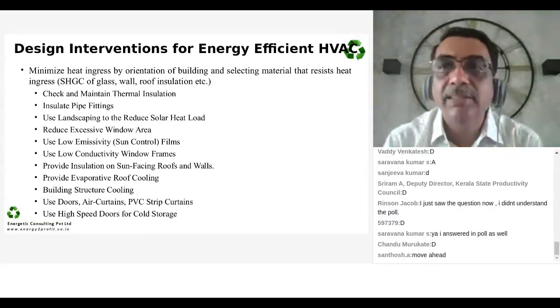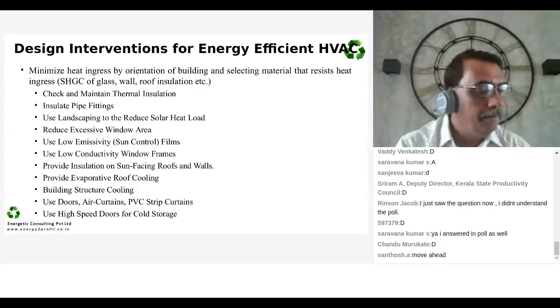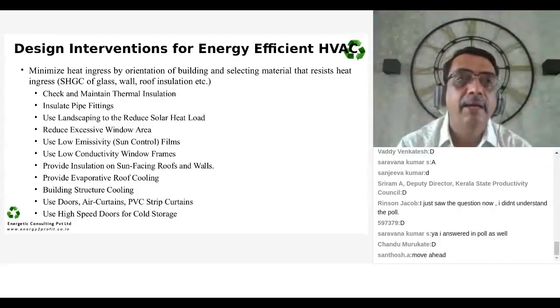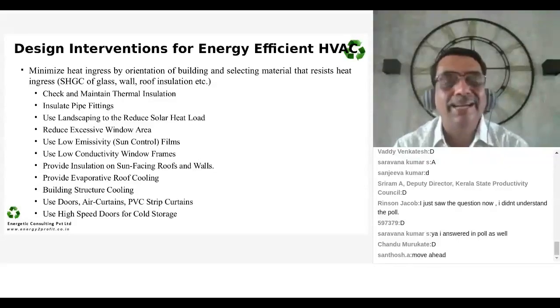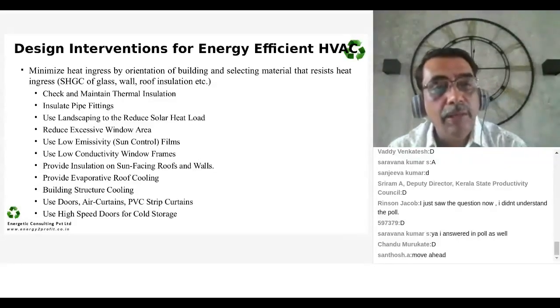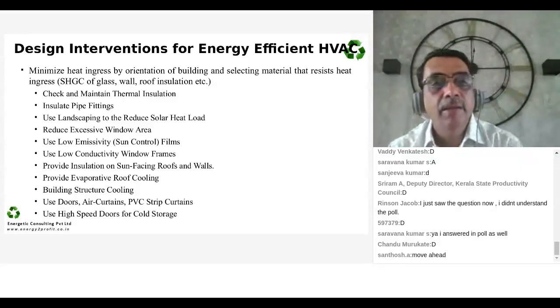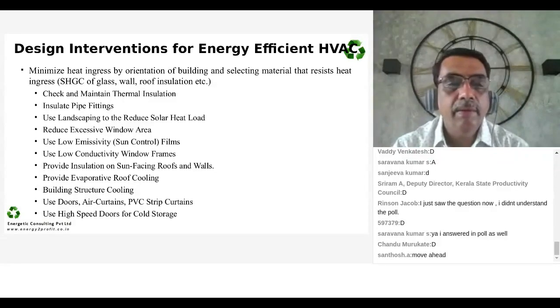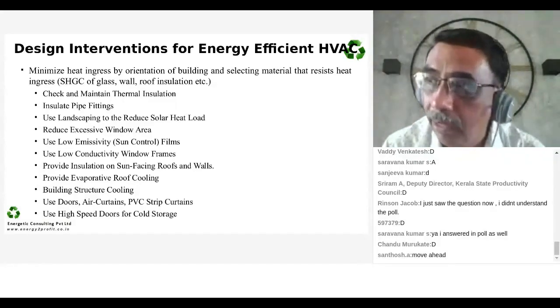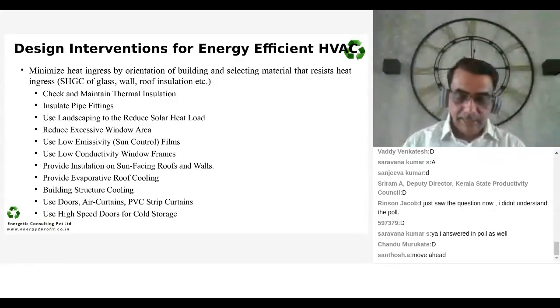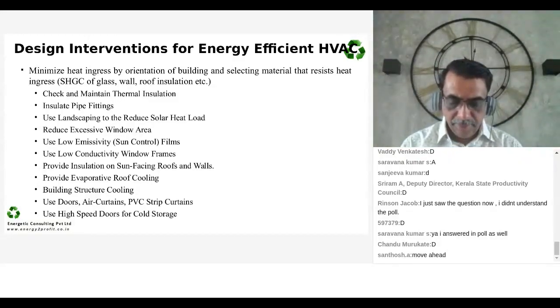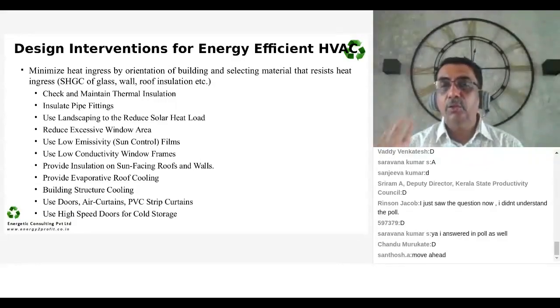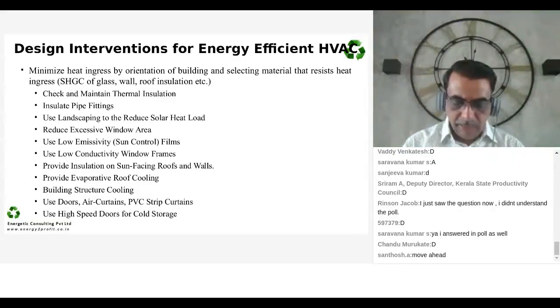So, what are the design interventions for an energy efficient air conditioning system? I'm not going to read them out, but just to summarize, there is a checklist of a lot of things: whether your window area is excessive, whether the window frames are conductive, whether the building's structure cooling is in place. I'm sure most of you may not have structure cooling. The trend now is that instead of cooling the air, people continue to cool the structure by even including cooling pipes inside the structure. That allows the structure to remain cool inside in spite of outside conditions.